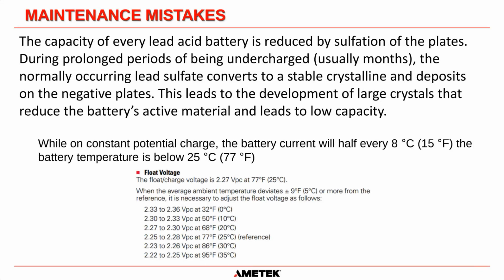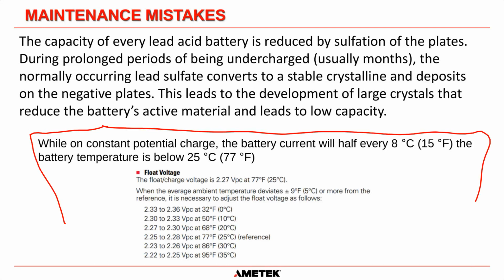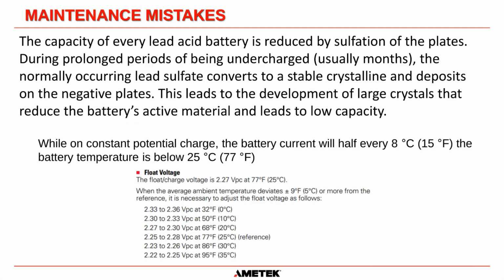So this bottom portion here is from a manufacturer, and it says, while on constant potential charge, the battery current will halve every 8 degrees Celsius or 15 degrees Fahrenheit. So what that's saying is, in the US, they say that you should charge your batteries at 77 degrees Fahrenheit. If your temperature went down 15 degrees to 62 degrees Fahrenheit and you didn't adjust the float voltage, then the battery current will halve, and therefore you won't be overcoming the internal chemical losses that are going on inside the battery, and the battery will start to discharge into sulfate slowly. So low temperature does affect the state of charge of the battery if you don't adjust the float voltage.